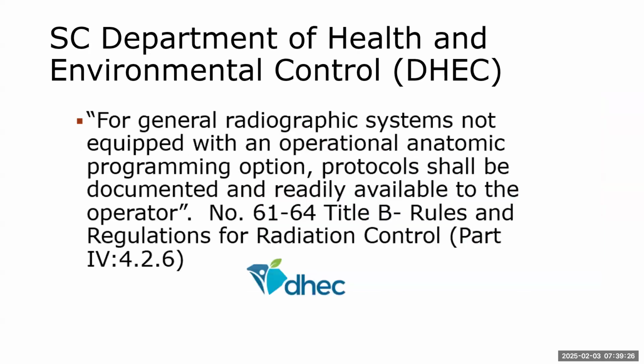So the South Carolina Department of Health and Environmental Control states that for general radiographic systems not equipped with an operational APR, protocols shall be documented and readily available to the operator. So what that says is, if your machine doesn't have APR, then there better be a technique chart readily accessible to that piece of equipment for you to use.